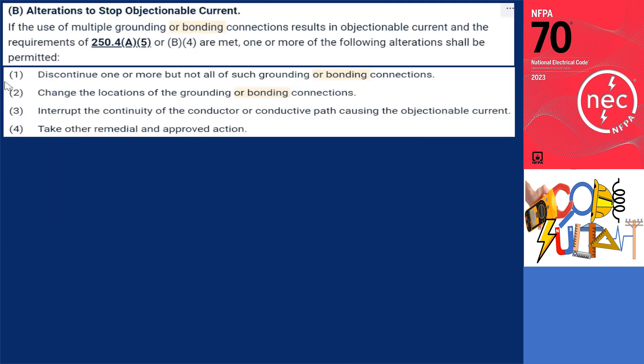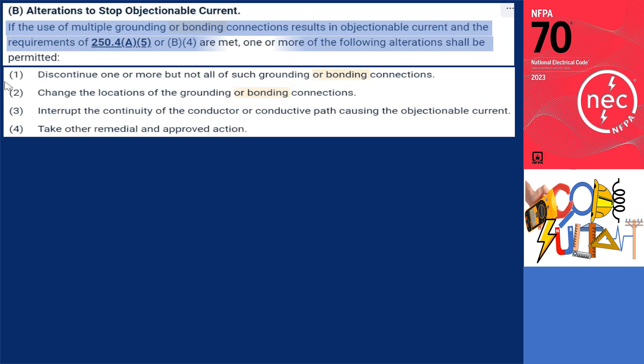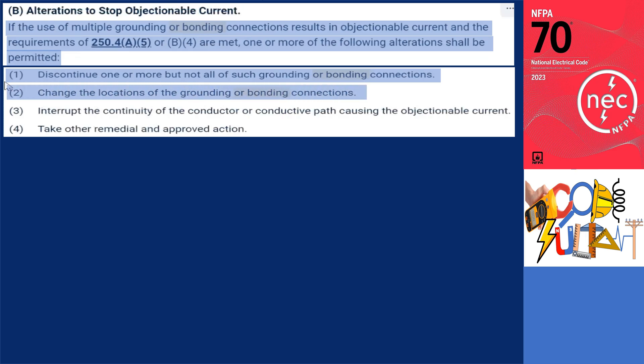What if an objectionable current exists in your system? Section 250.6B is about alterations to stop objectionable current and states that if the use of multiple grounding or bonding connections results in objectionable current and the requirements of 250.4A5 or B4 are met, one or more of the following alterations shall be permitted: discontinue one or more, but not all, of such grounding or bonding connections; change the locations of the grounding or bonding connections; interrupt the continuity of the conductor or conductive path causing the objectionable current; or take other suitable remedial and approved action.